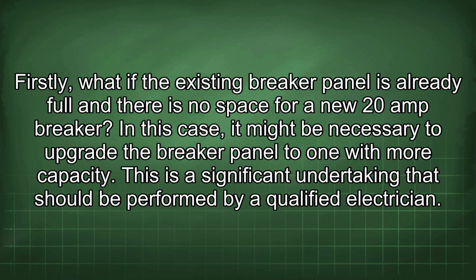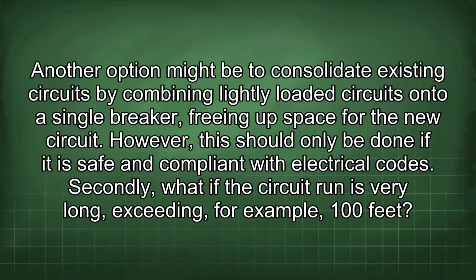Firstly, what if the existing breaker panel is already full and there is no space for a new 20 amp breaker? In this case, it might be necessary to upgrade the breaker panel to one with more capacity. This is a significant undertaking that should be performed by a qualified electrician. Another option might be to consolidate existing circuits by combining lightly loaded circuits onto a single breaker, freeing up space for the new circuit. However, this should only be done if it is safe and compliant with electrical codes.